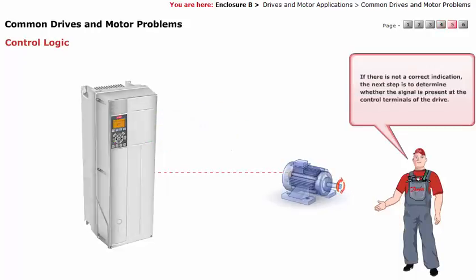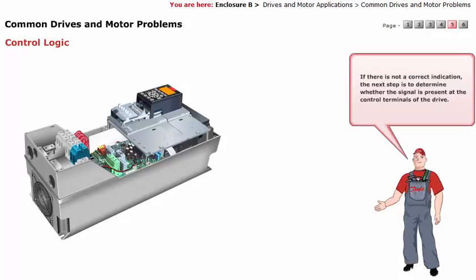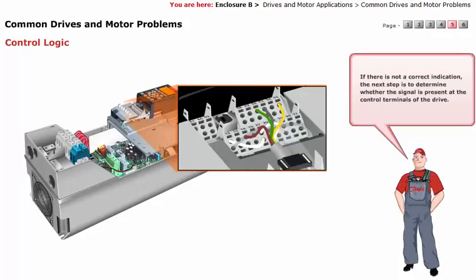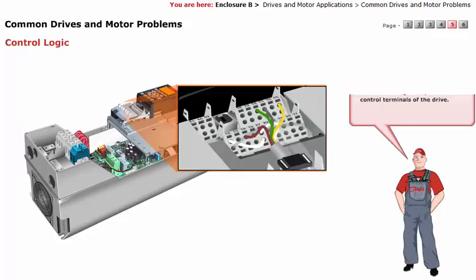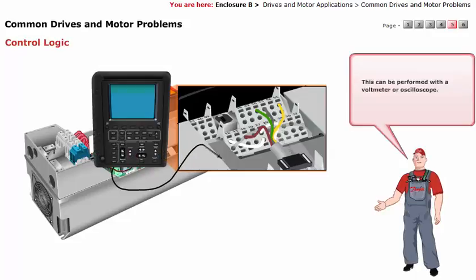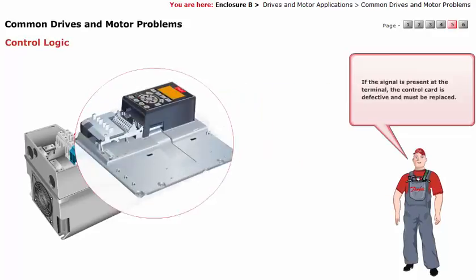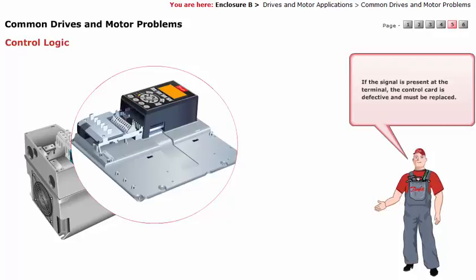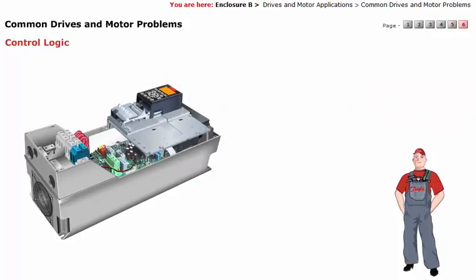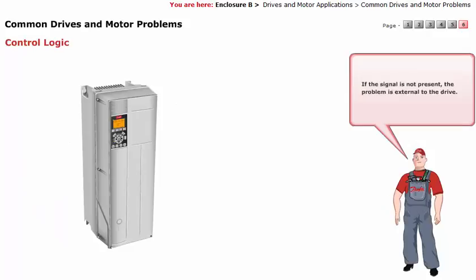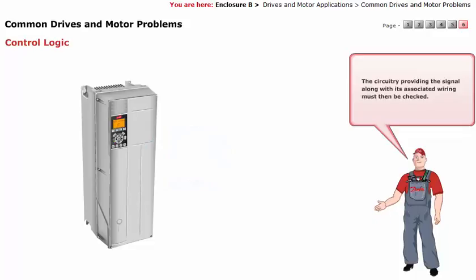If there is not a correct indication, the next step is to determine whether the signal is present at the control terminals of the drive. This can be performed with a voltmeter or oscilloscope. If the signal is present at the terminal, the control card is defective and must be replaced. If the signal is not present, the problem is external to the drive, and the circuitry providing the signal along with its associated wiring must then be checked.